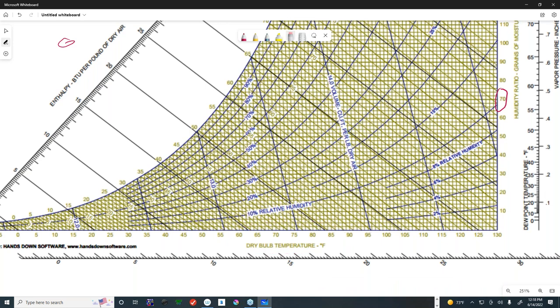Okay, these numbers over here on the slanted part of the chart are considered wet bulb temperatures. So there's that wet bulb; we're starting to introduce that. And then, like I said before, if we know any two points on the psychrometric chart, we can find the other points. But let me just point out what some of the other lines here mean. See these curved lines right here? These are lines of constant relative humidity. I just circled the 50% relative humidity line. There's 40%, 30, and so on. There's 60%. Those are all the different values for relative humidity. So we can easily see the relative humidity on this chart.